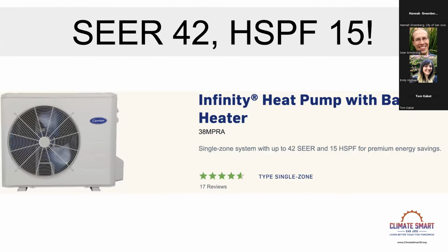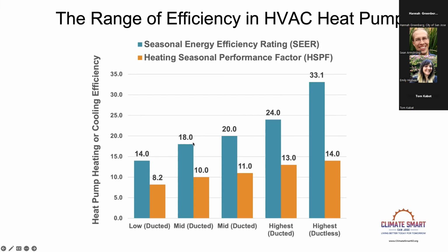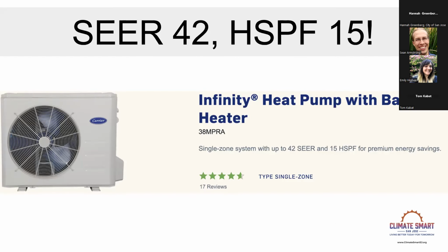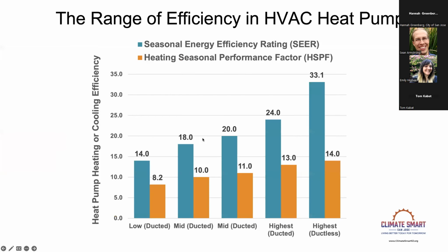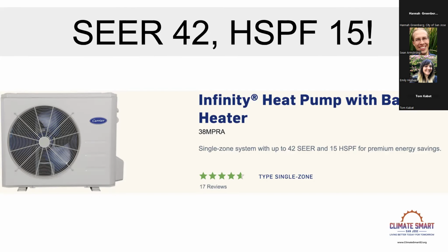And I lied, here's the really most efficient. It's just come out from Carrier. Carrier's got this SEER 42, HSPF 15. I want to remind you, the least efficiency you can put in is a SEER 14, and this is a 42. So that's 1/3 as much energy being used by this 1 ton heat pump, and HSPF 15 means this is roughly half as much space heating energy in the winter. Maybe it's not quite, maybe 60% or 55%, but it's almost half as much.